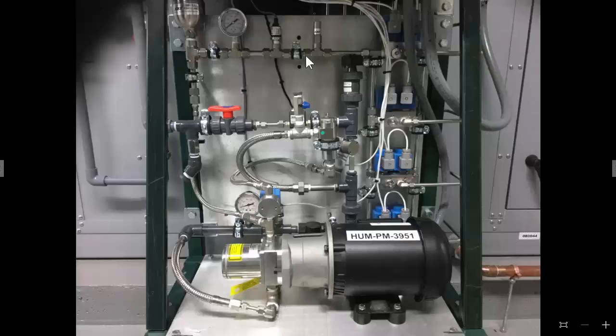Now, I did talk about this pressure relief valve here a little bit, and that's set around 1300, 1400 psi, and that is there just in case there's another failure with this particular pressure transducer and the pressure gets too high within the system. We've got to be able to relieve that pressure, and that's how it's done through that relief valve. Now, it's going to be pretty rare that that ever happens, because if something did happen to this pressure transducer, it would probably go out of range and it would shut the system down, even though it may not actually be out of range. Or it just is going to cause the system to do enough funny things that it'll, like I said earlier, be out of range and shut the system down. Now, I have not had that happen yet.